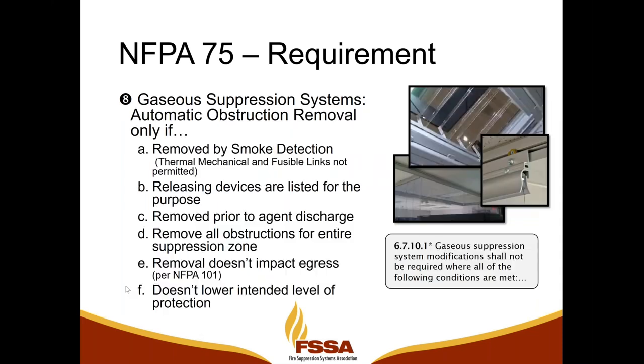Point eight is, where there are gaseous systems, automatic obstruction removal. Again, the same points as before. Remove the obstructions via smoke detection. The partition releasing devices are listed for the purpose. It has to be done prior to the agent discharge. You have to remove the entire zone. It can't impact egress, and it can't lower the level of fire protection.